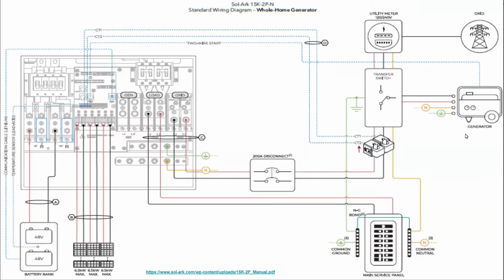Very large generators, such as sometimes we're using the 15K and three-phase configurations, can overpower the system and therefore keep getting backfed. Ironically, the other example would be ultra premium generators. I'm not as familiar with the Briggs and Stratton line, but for example, Generac has an EcoGen line that has an incredibly clean grid signal, and then it shows up as grid power.